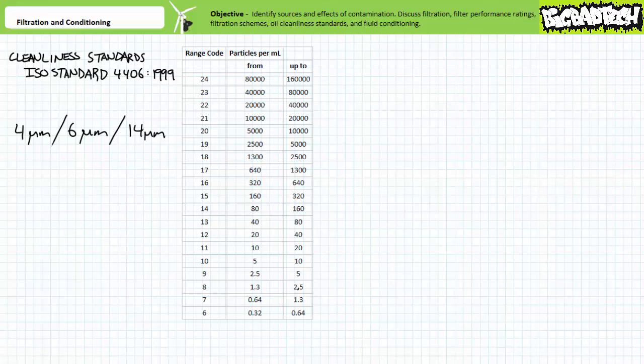Finer applications like servo valves might call for oil with higher cleanliness standards. For example, a servo valve might call for oil using the 16-14-11 ISO cleanliness standard. This means anywhere from 320 up to 640 particles greater than 4 microns, but less than 6 microns are present per milliliter. Anywhere from 80 up to 160 particles greater than 6 microns, but less than 14 microns are present per milliliter. And anywhere from 10 up to 20 particles greater than or equal to 14 microns are present per milliliter. Note the lower bin numbers indicate less particles of a given size per unit volume because the oil is cleaner.